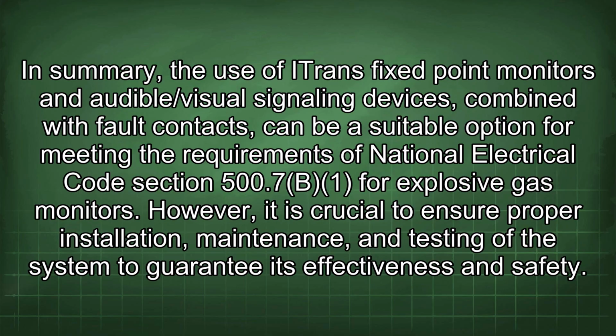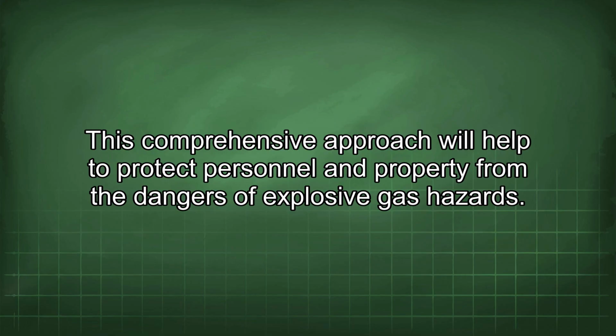In summary, the use of ITrans fixed-point monitors and audible/visual signaling devices, combined with fault contacts, can be a suitable option for meeting the requirements of National Electrical Code Section 500.7(B)(1) for explosive gas monitors. However, it is crucial to ensure proper installation, maintenance, and testing of the system to guarantee its effectiveness and safety. This comprehensive approach will help to protect personnel and property from the dangers of explosive gas hazards.